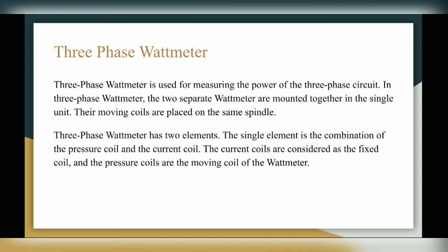Working principle of three-phase wattmeter. It works on the principle that a torque develops on a current-carrying conductor when it is placed in a magnetic field. When the measured power passes through the moving coils, the torque develops on the coil. The torque is a type of mechanical force whose effect can deflect an object in a circular motion. So the principle is the same as that of the single-phase wattmeter: a current-carrying conductor is placed in a magnetic field, then it experiences a force.